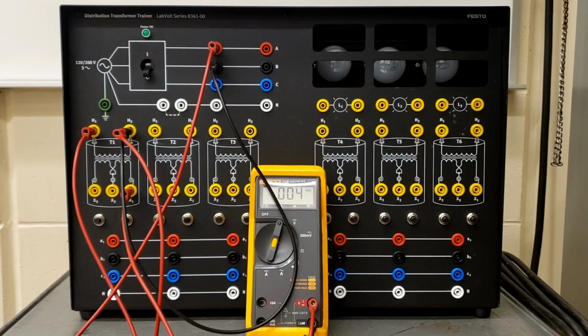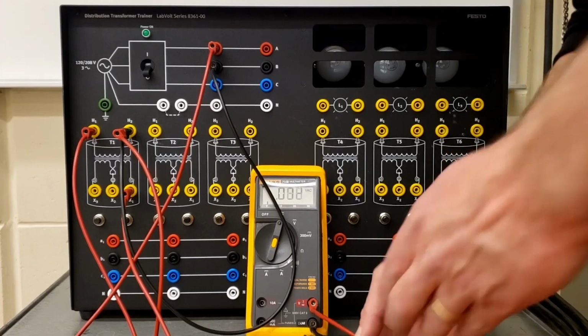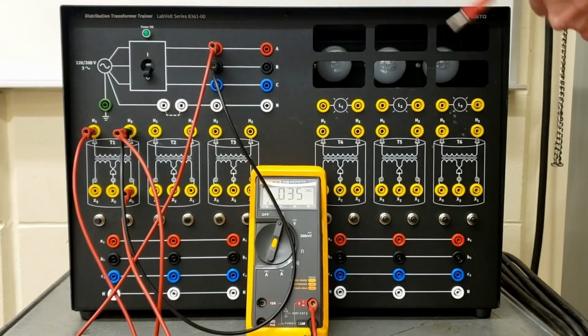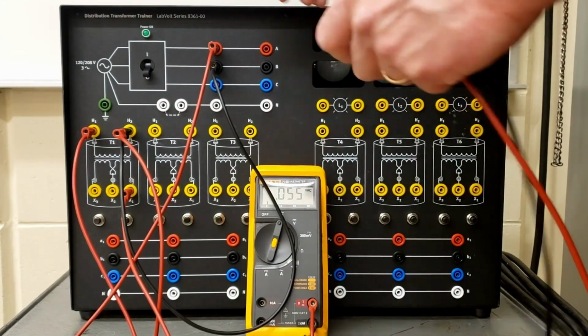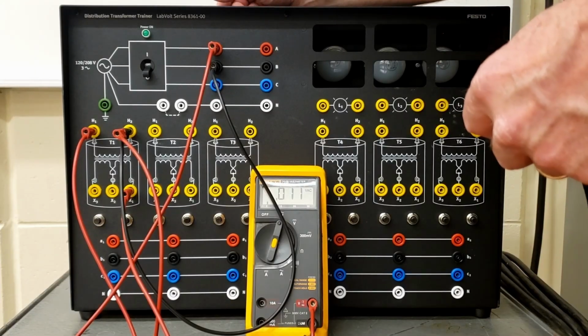And what are we looking at? It says turn on the distribution transformer trainer, determine if the transformer is connected with additive or subtractive polarity by observing the relative brightness of the lamps, or by measuring the voltage between terminals H1 and X2. You use 2 lamps in series if you determine the voltage by observing the relative brightness of the lamp. So we may not want to work on the wording there. First thing is we would want to look at the voltage between H1 and X2. So between H1 and X2.